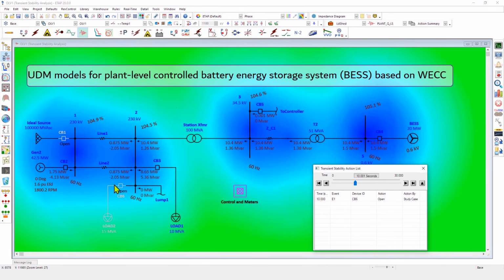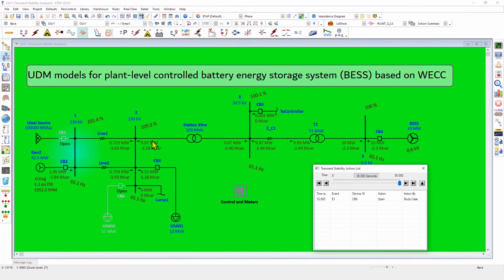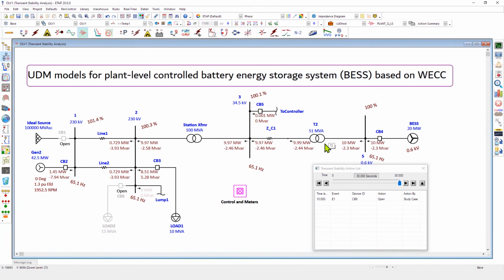This is corresponding to some kind of load rejection or load shed in the system. And at that moment in time, we can observe a significant overvoltage in the network as anticipated because we have lost load in the circuit, and our control system must therefore compensate for this overvoltage condition. We can then move to the end of our simulation and see the final result, and we can see that the voltages have recovered and the blue areas shown with the color contouring have essentially dissipated on our one-line diagram. We can simply turn the contouring on and off by using the contour button.